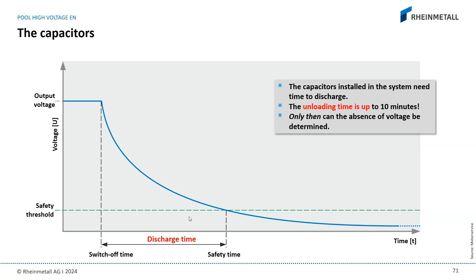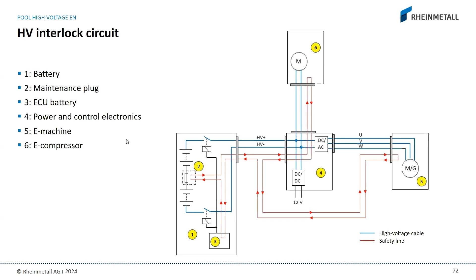If you are using the safety line, the interlock line, to disconnect, you will discharge the capacitors in 1.2 or 1.3 seconds. So it's very, very fast. This is what I mean when I say it's not controlled discharging of the capacitors.